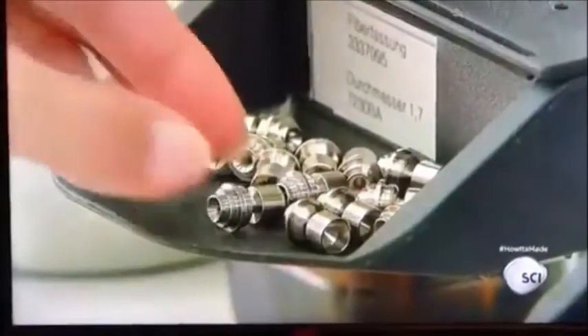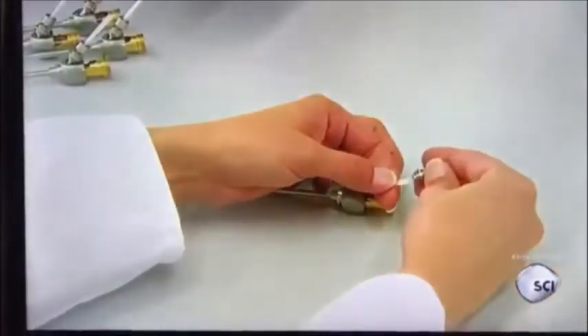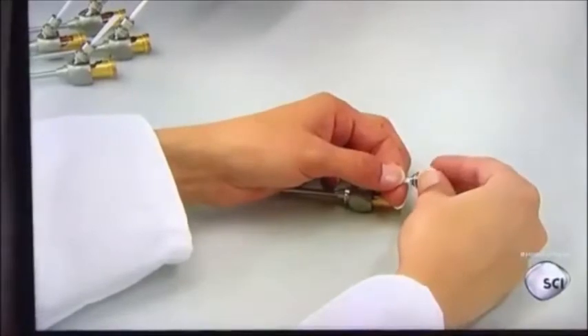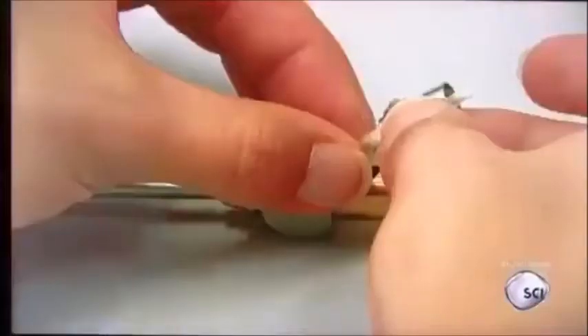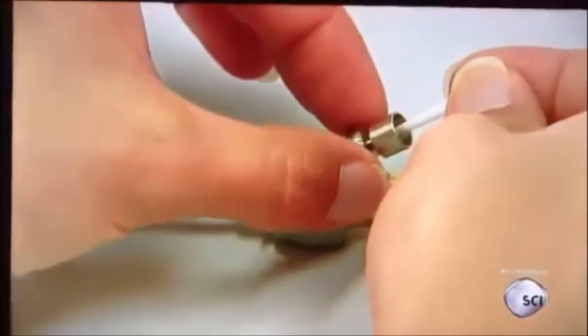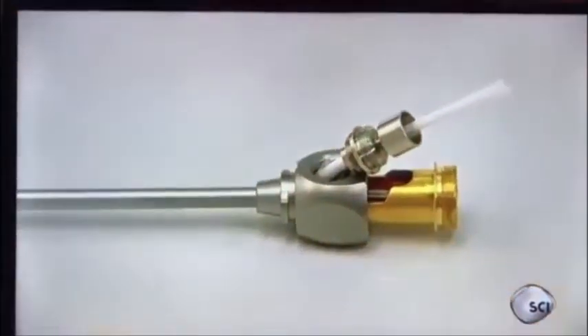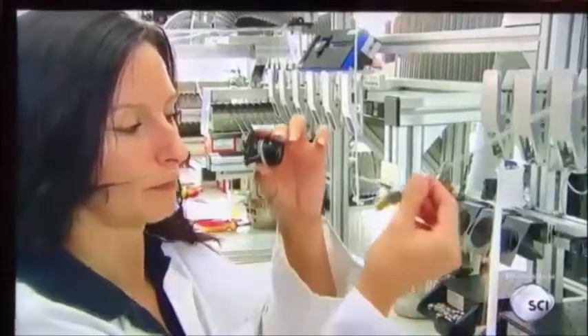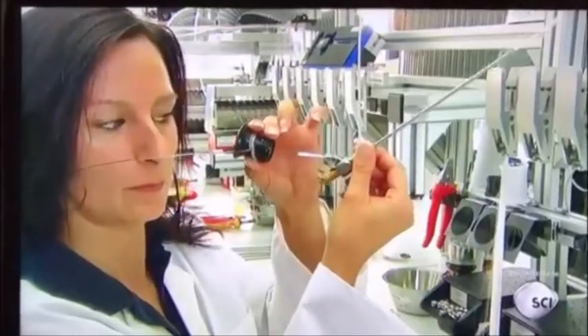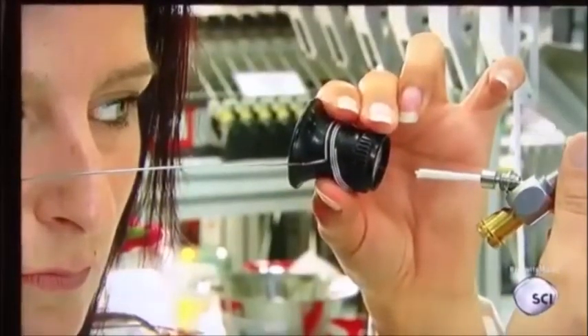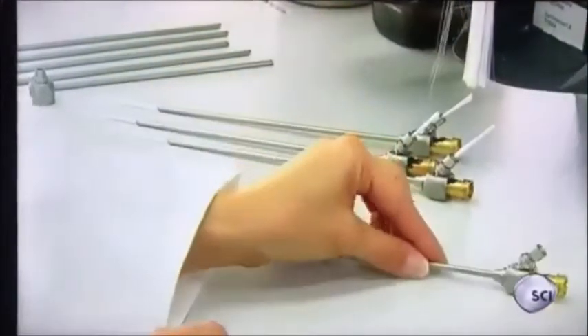They attach a stainless steel adapter. This will connect the light cable from the operating room light source to the endoscope, transferring light to the optical fibers inside the endoscope. A worker inspects those fibers under magnification for black spots. Black spots indicate broken fibers, which would interrupt the transmission of light.